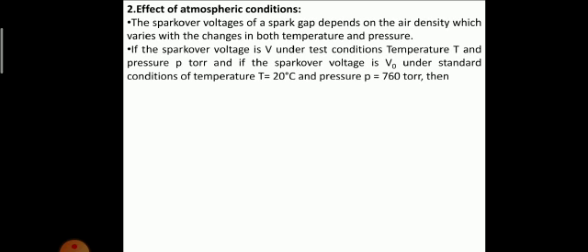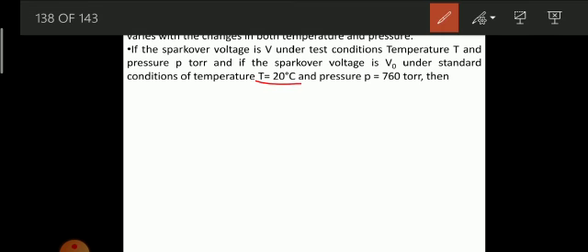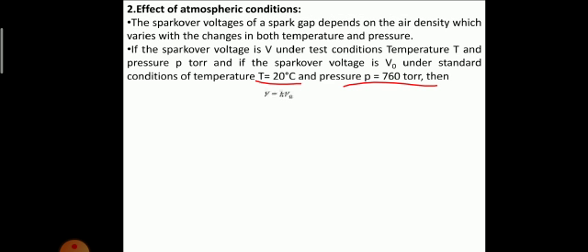So if the spark over voltage under test conditions is V, T is the temperature and P is the pressure in torr. If the spark over voltage under STP, standard temperature and pressure, with temperature being 20 degrees centigrade and pressure being 760 torr, is V0, then V is given as K into V0, where K is a function of the air density factor D, which is given as D is equal to P divided by 760 into 293 divided by 273 plus T.